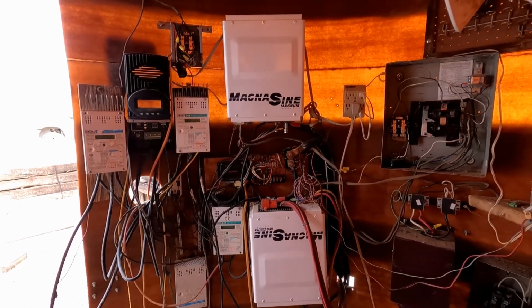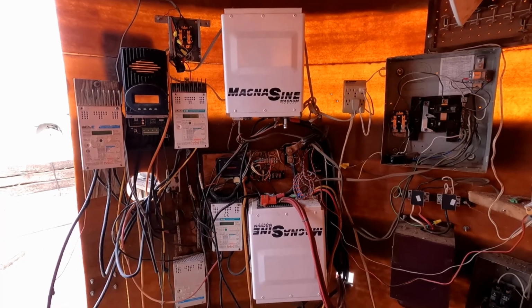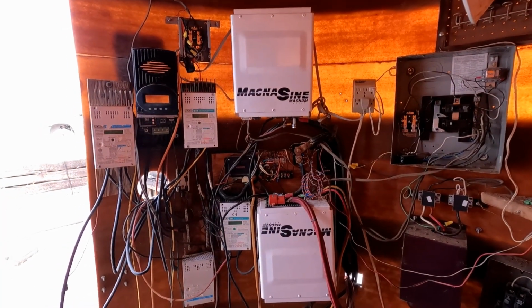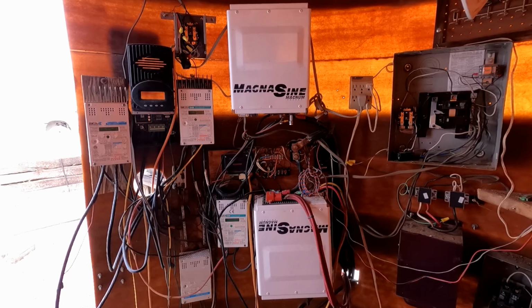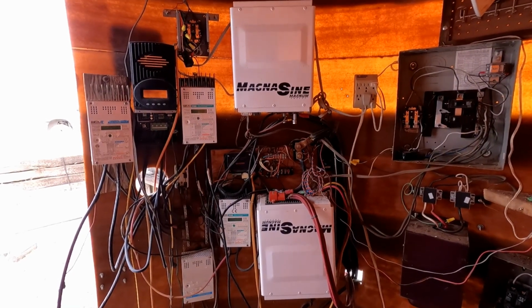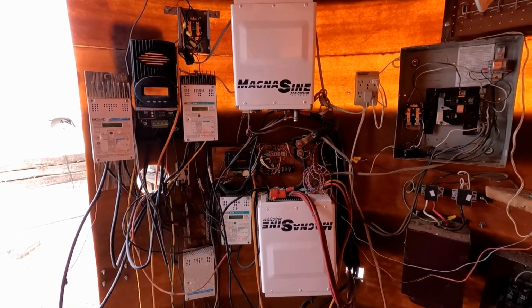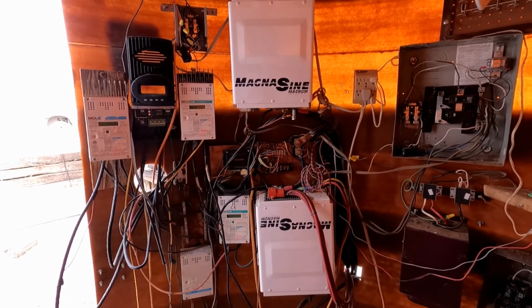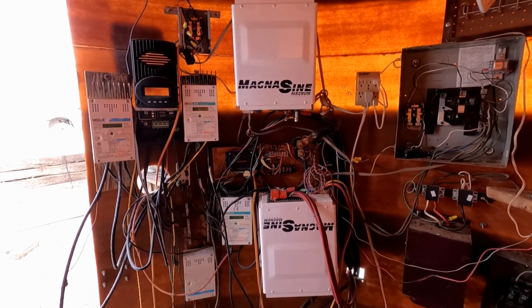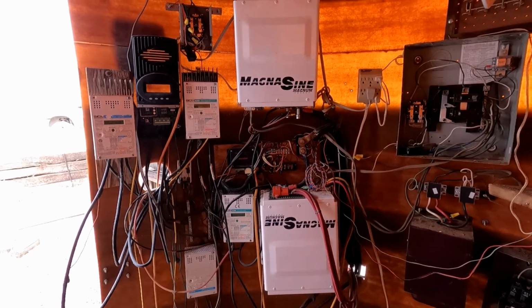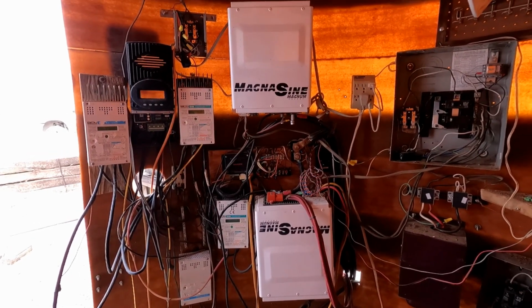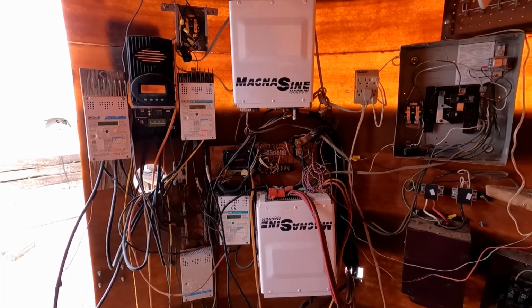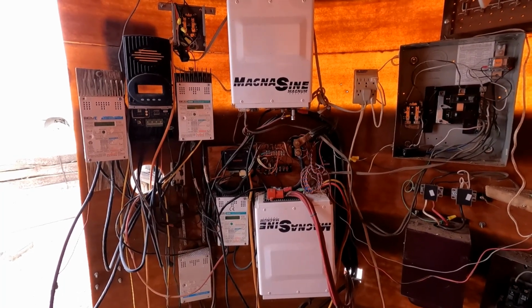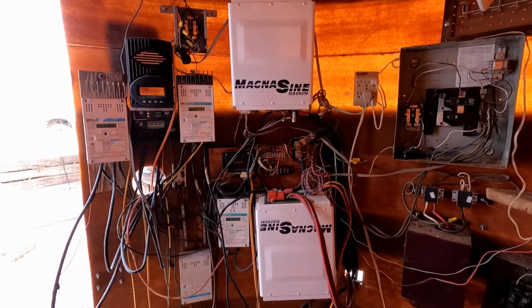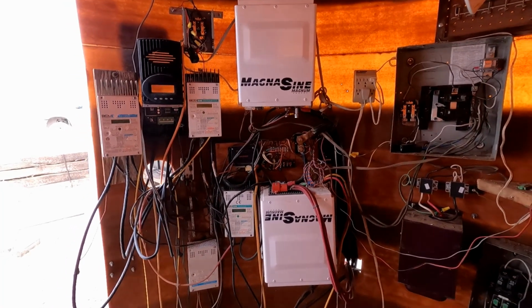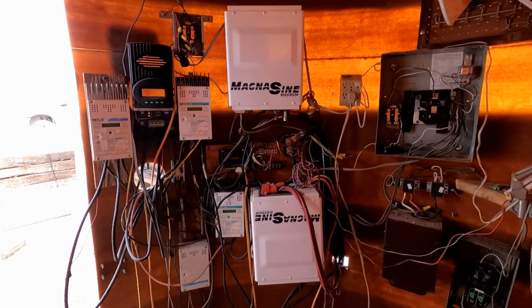At the same time, in a normal system, the inverters are then consuming a lot of power in charging the batteries and in addition to supplying the house, depending on how much you're using. So eventually when the batteries reach the full charge point, the inverters are going to turn the generator off. But prior to turning off the generator, they disconnect the AC feed from the generator. And then eventually they turn the generator off. Now this disconnection of AC feed from the generator can be a significant factor.